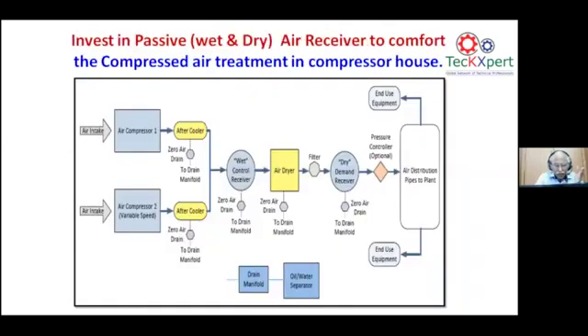So investing in passive receivers on the dry side and the wet side, these two are more important now. Every compressor OEM says one receiver is enough, but it's not enough. We are now definitely supposed to have two receivers. One is a wet receiver, the other one is a dry receiver. The wet receiver will take care of the compressed air pulsations. The dry receiver will take care of the process air pulsations, and they will work in tandem to see that the compressed air is always kept at a steady flow and pressure.